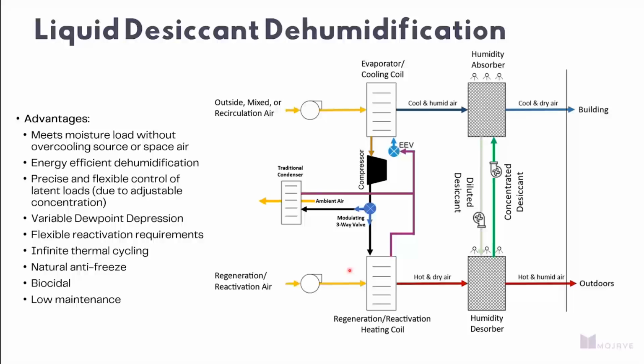Now, for control of the dew points, we're able to do active dew point reset. The way we achieve that is by regulating our hot gas via this modulating three-way EEV. For days where we need more dehumidification or peak dehumidification, we're going to be routing a majority of our hot gas off the compressor into this regeneration coil to drive more moisture out of our desiccant, to heighten the concentration and lower the vapor pressure further to pull more moisture out of the air in this humidity absorber.